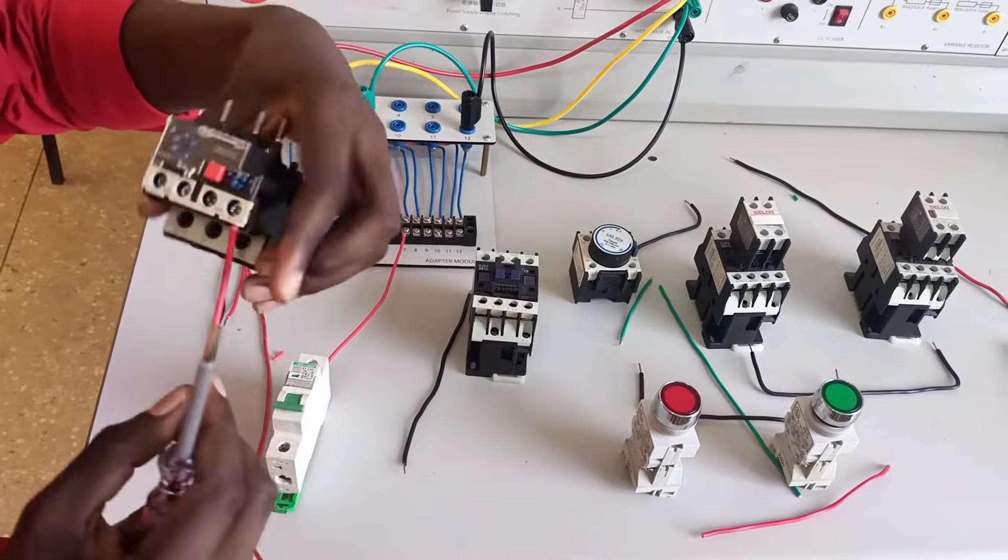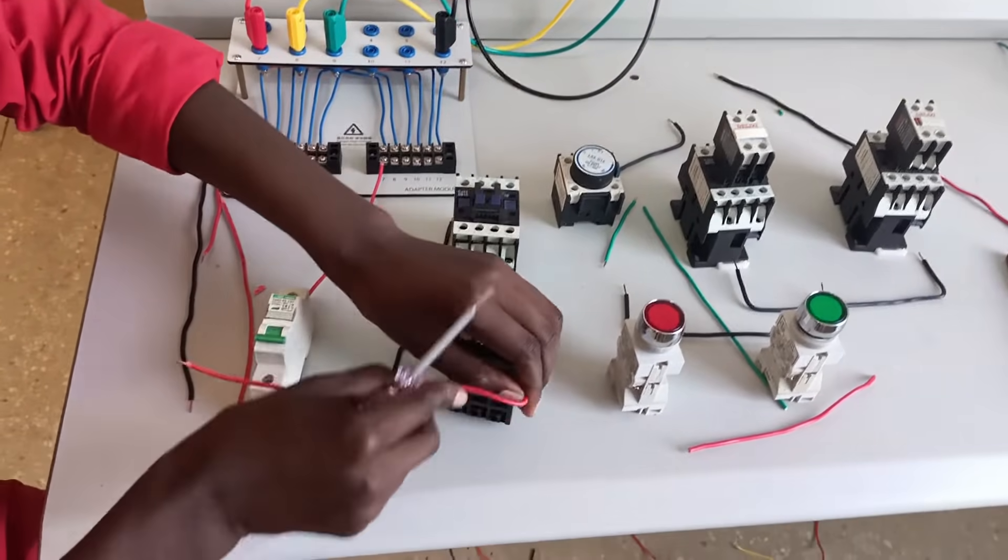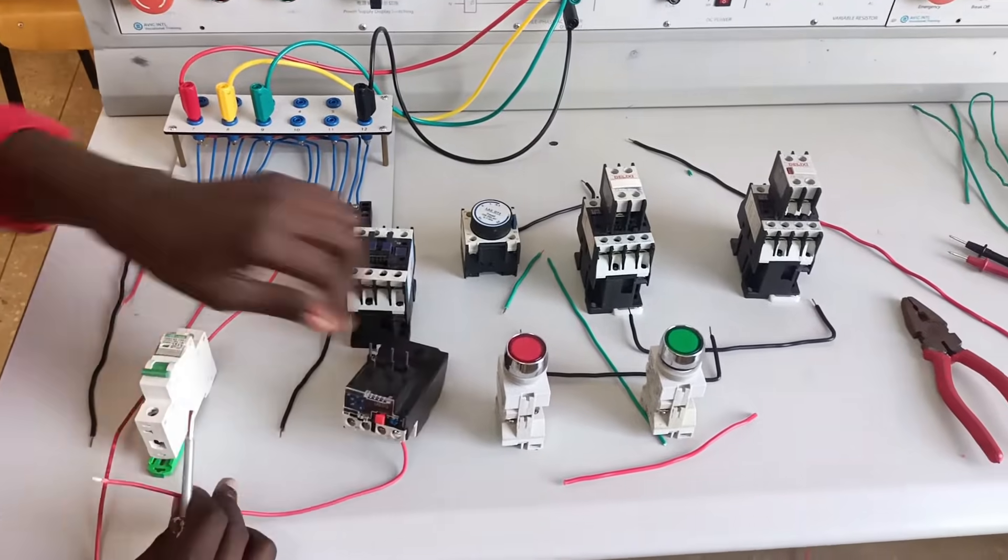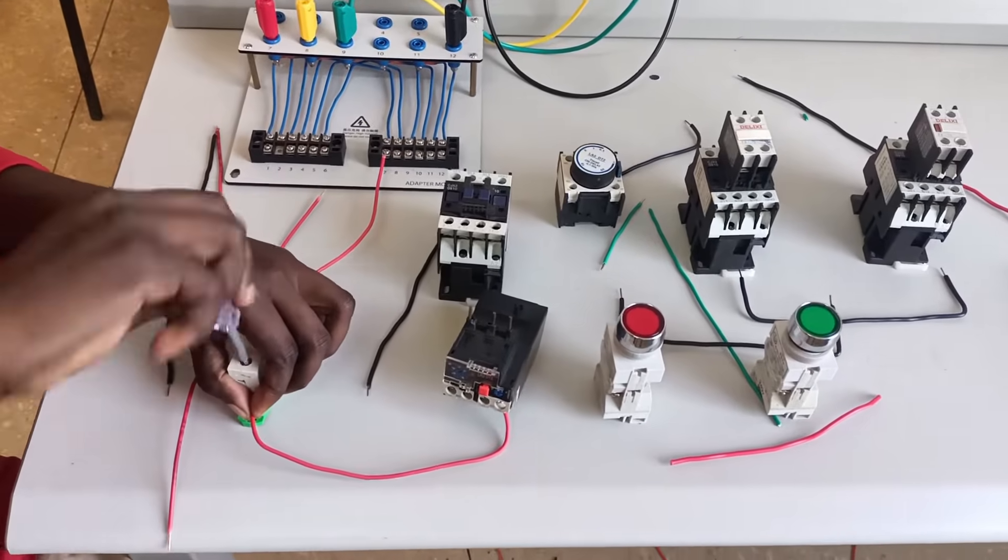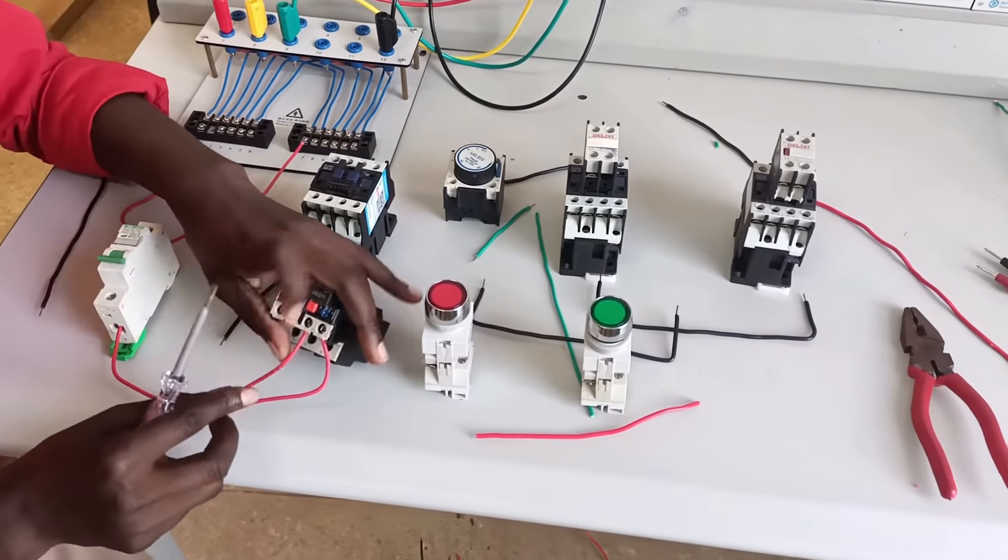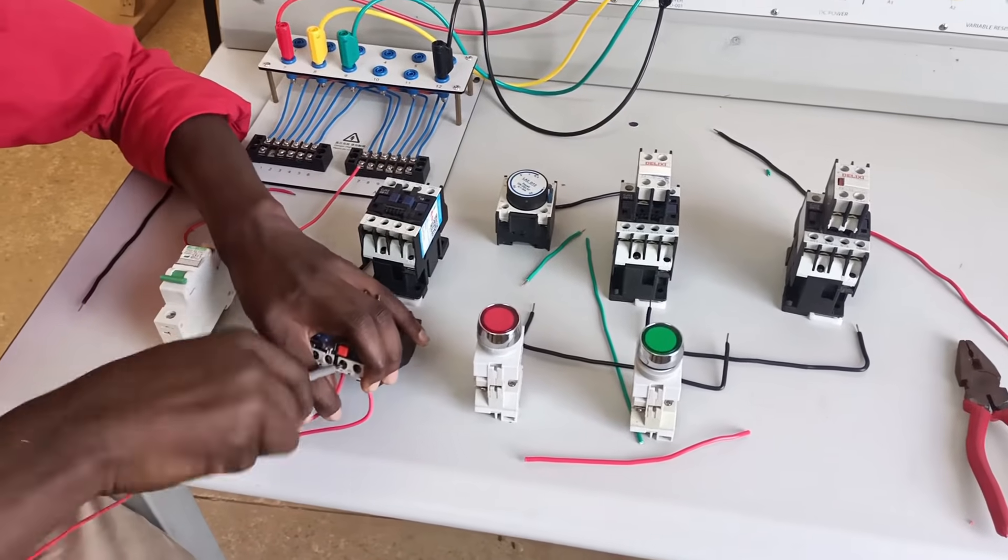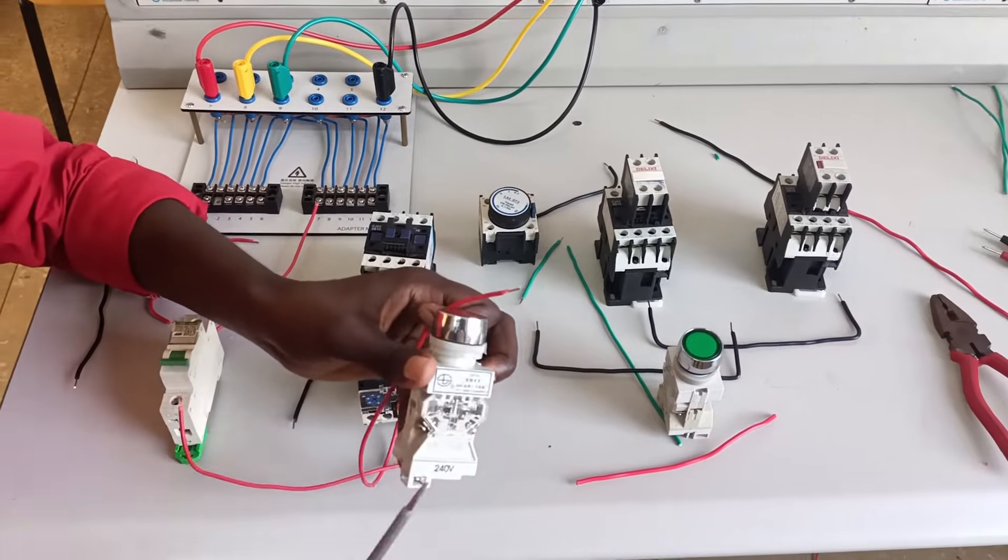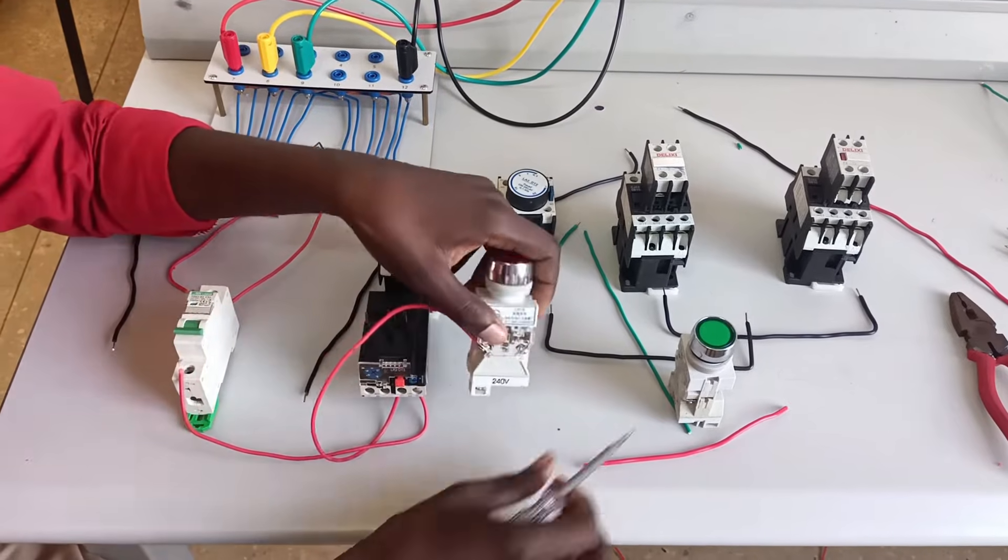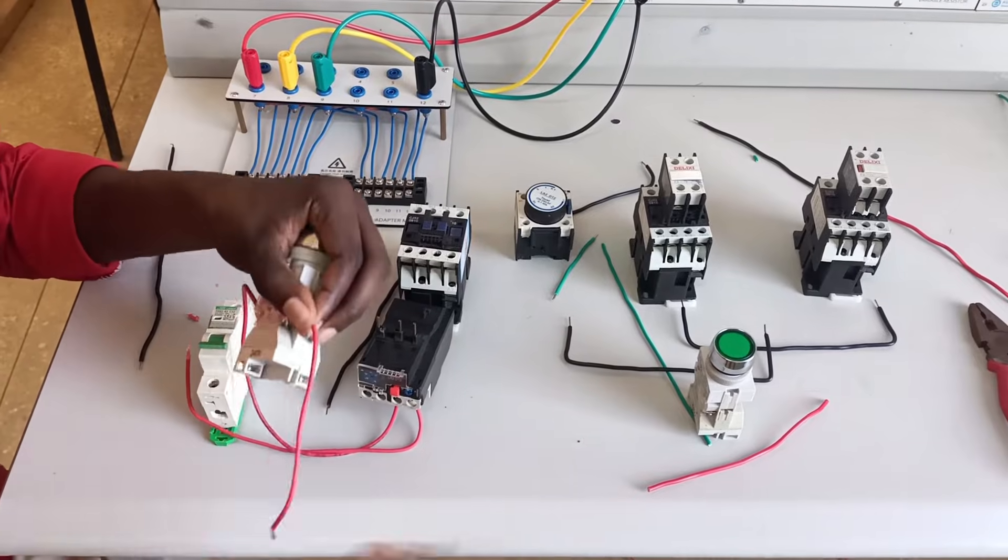From the thermal overload relay to the circuit breaker, that's pin 95, and then pin 96 of the thermal overload relay will connect to the NC push button, that's the stop button, the one you see in red. So that's pin 96 of the thermal overload relay. For this case, those are the two contacts we are going to use in the thermal overload relay.